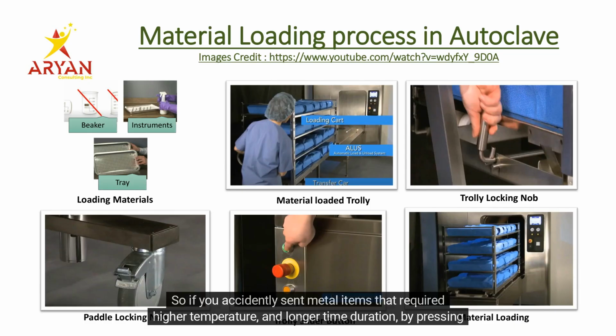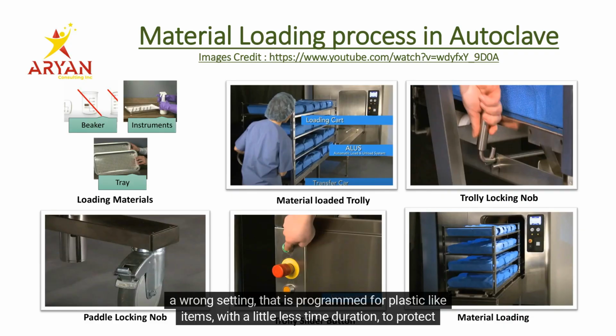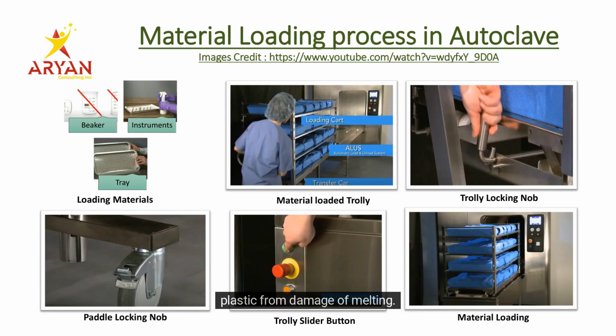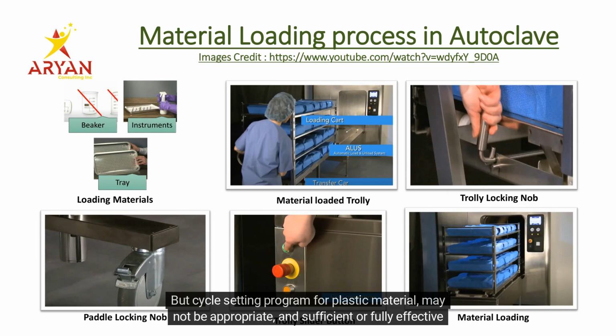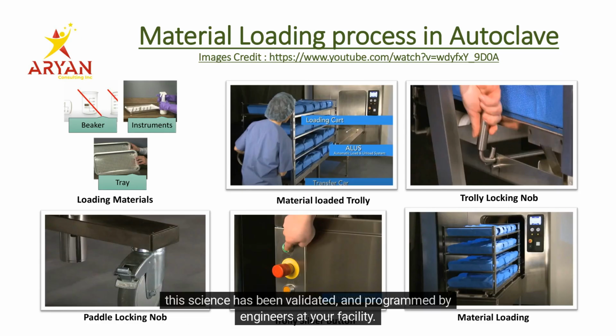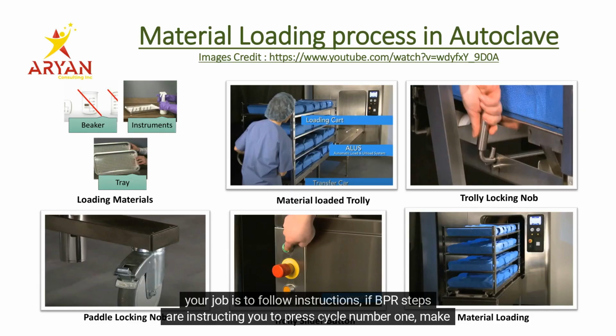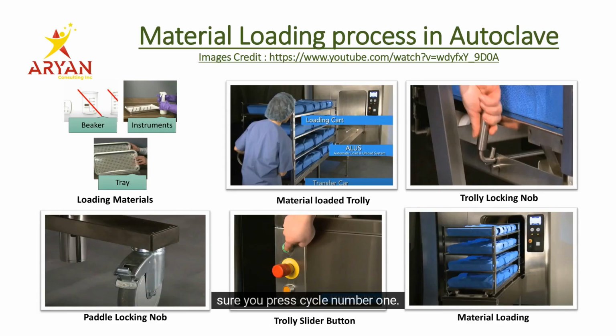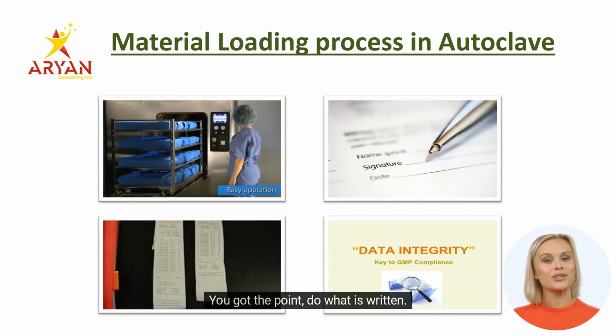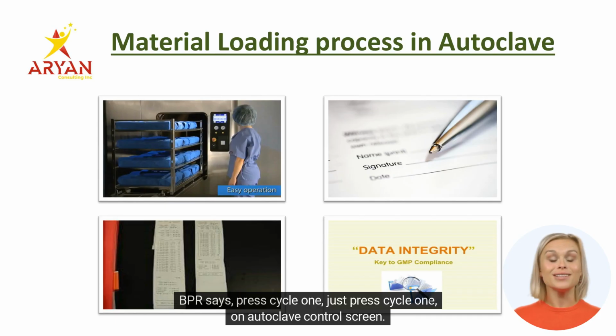So if you accidentally set metal items that require higher temperature and longer time duration by pressing a wrong setting that is programmed for plastic-like items, with a little less time duration to protect plastic from damage of melting, the cycle setting programmed for plastic material may not be appropriate and sufficient or fully effective for the metal autoclave cycle. This science has been validated and programmed by engineers at your facility. Your job is to follow instructions. If BPR steps instruct you to press cycle number 1, make sure you press cycle number 1. You got the point, do what is written. If the BPR says press cycle 1, just press cycle 1 on the autoclave control screen.